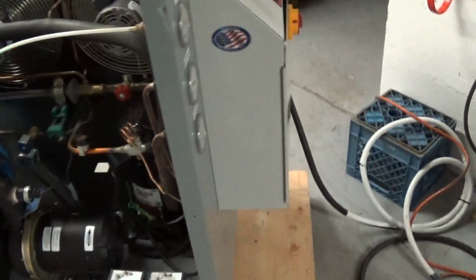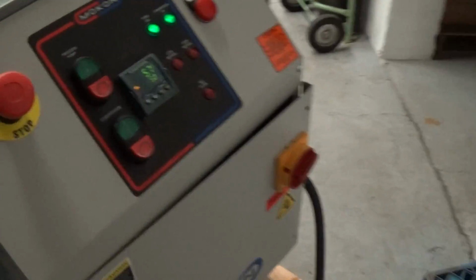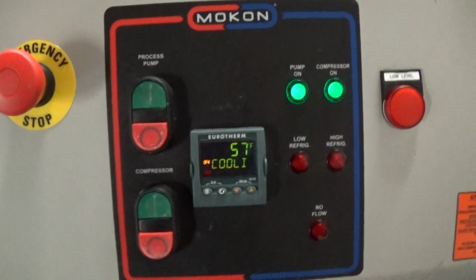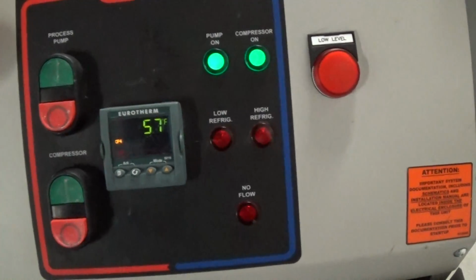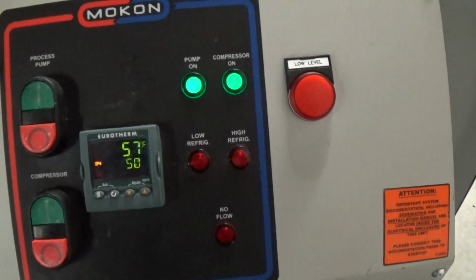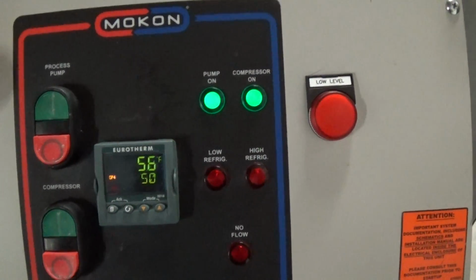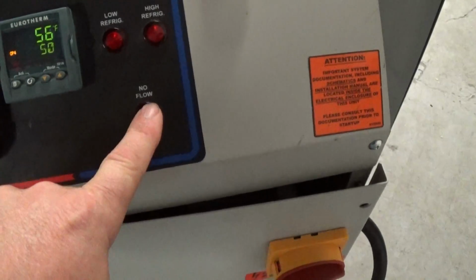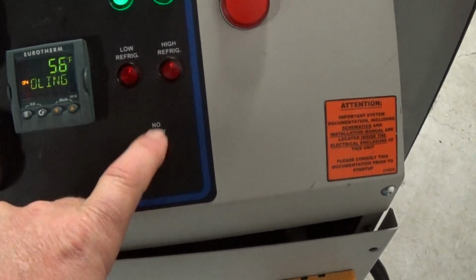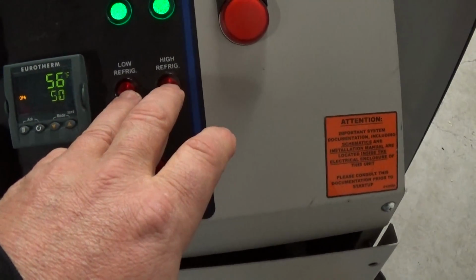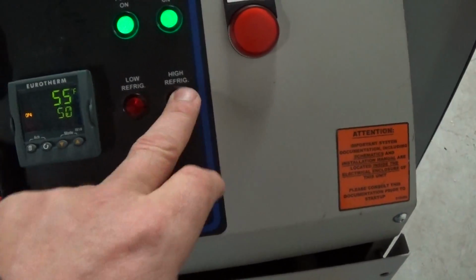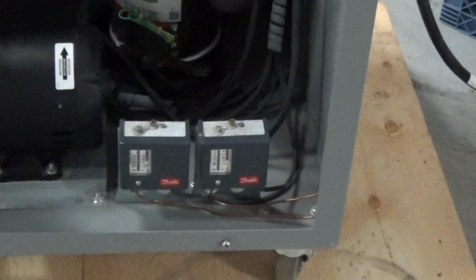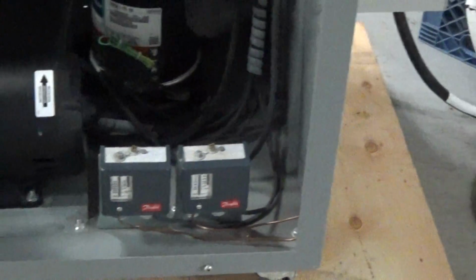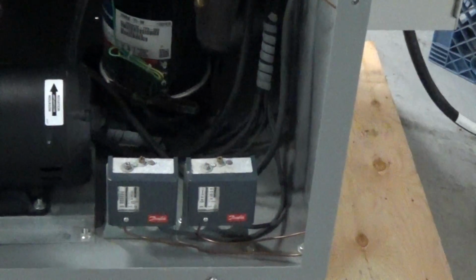So once your compressor is on, it stays on while we're chilling, and maintains the temperature by cycling that hot gas bypass and the liquid line solenoid valve at the same time. We have a flow switch in the unit, so if there's no flow, this fault will come out. And we have two warning lights, low refrigerant and high refrigerant. These are your low and high refrigerant gauges. Don't adjust those. Talk to us or Mokon before you try adjusting them.